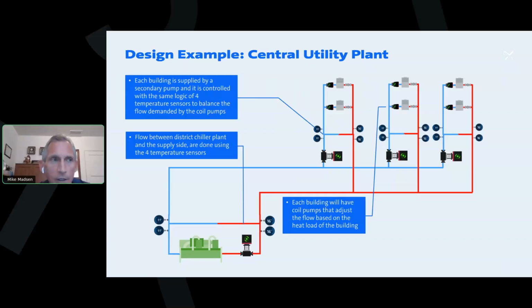So you could, in most cases, keep that primary skid on a primary secondary, as long as we can add those 4 temperature sensors for control. And then change the primary pump skid later when budget allows for it. I see. Ideally, though, you would change it, but maybe not the size, just change the pumps. Yeah, because then it has integrated controls, and then they can't override them.